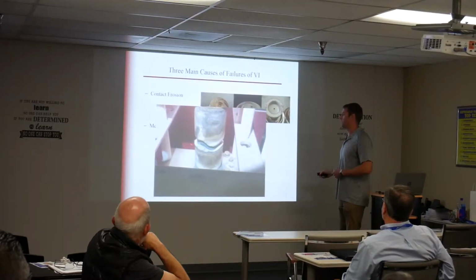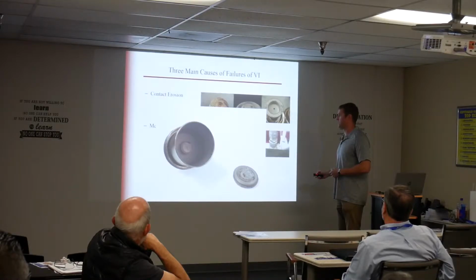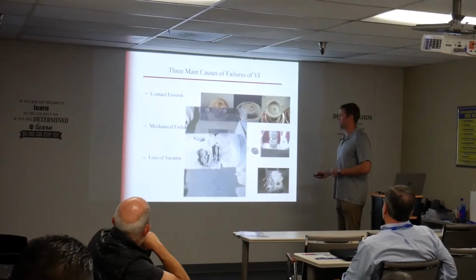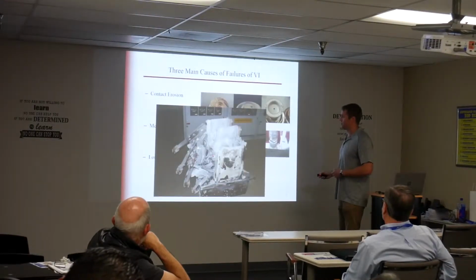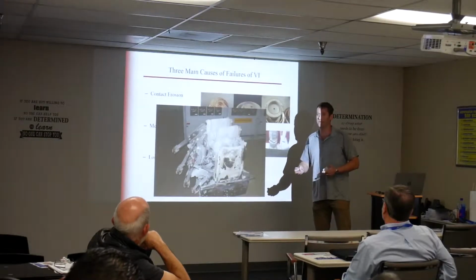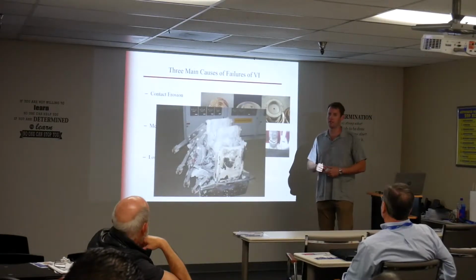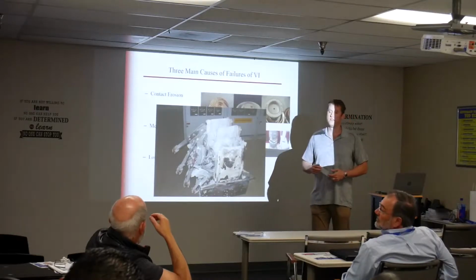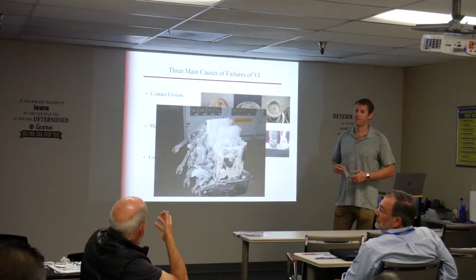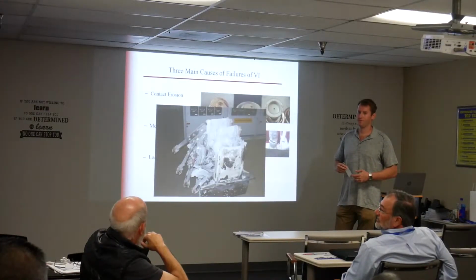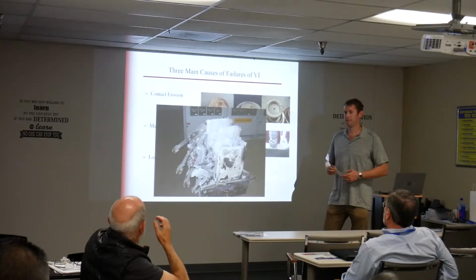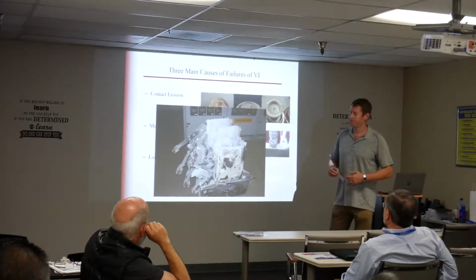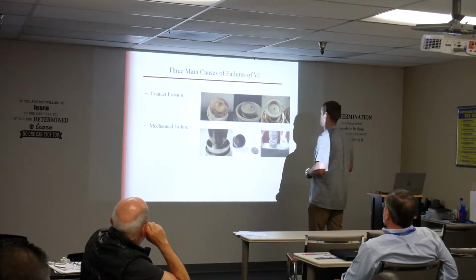Most of them don't have a ton of operations. And then 20 years down the line, eventually, there's nothing you can do. 20 to 30 years is how long it takes enough gas to leak in. And if you remove the load before you open the contacts, you have very minimal wear. Yeah, that's how most people do it. Yep, you're exactly right.